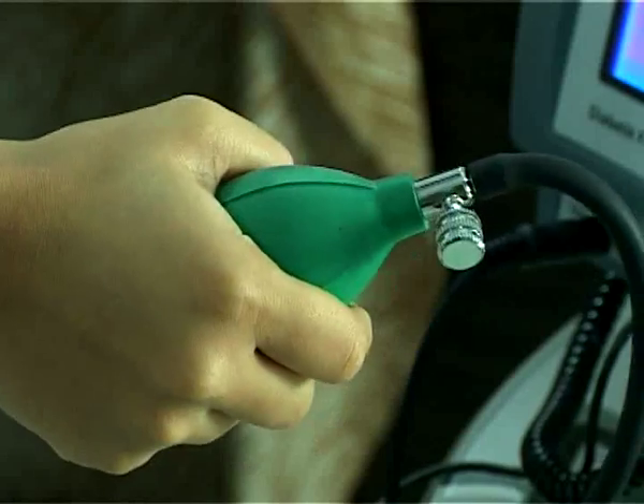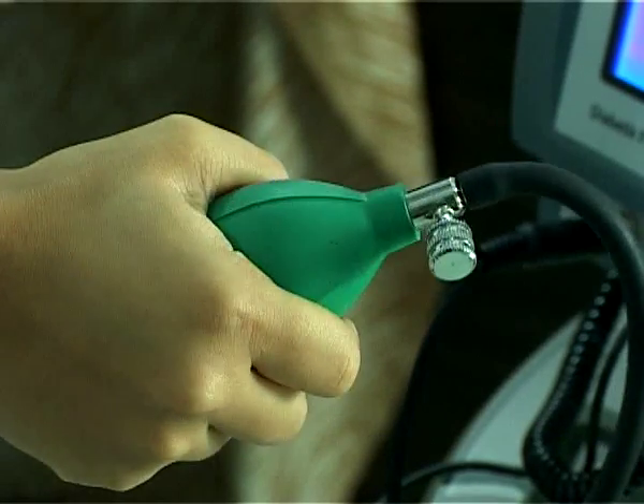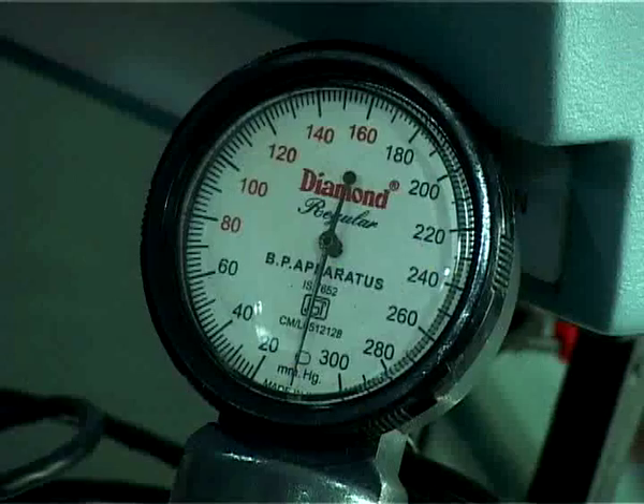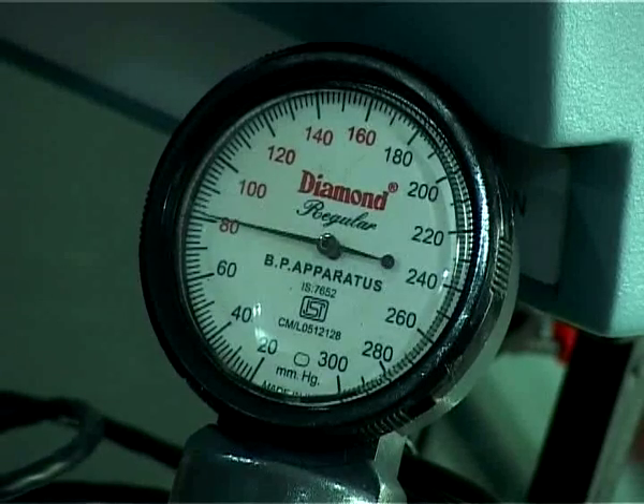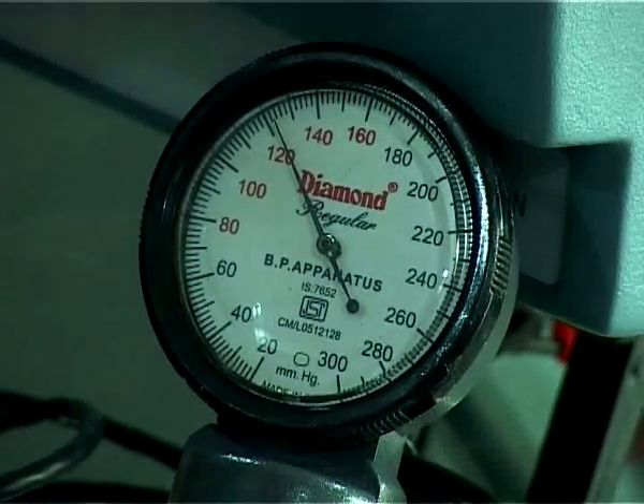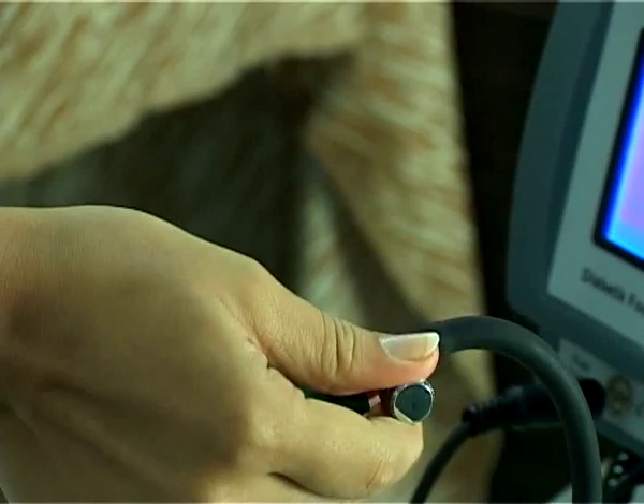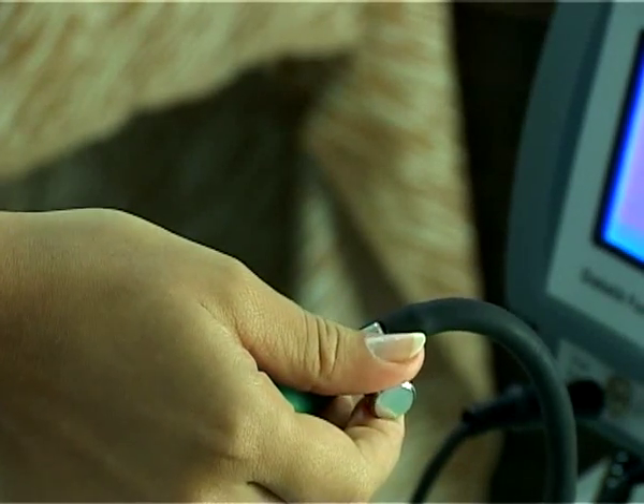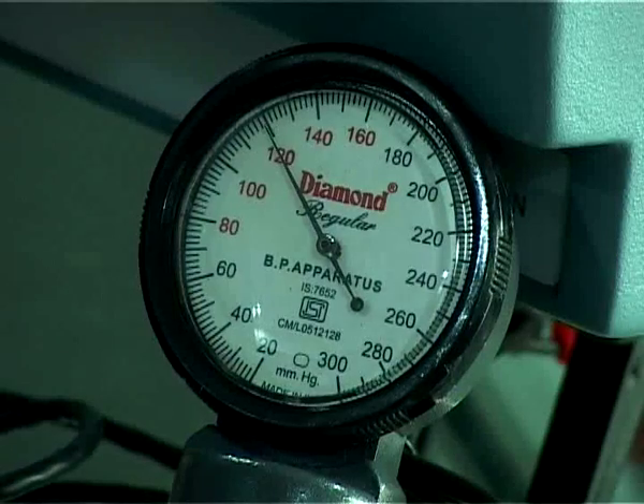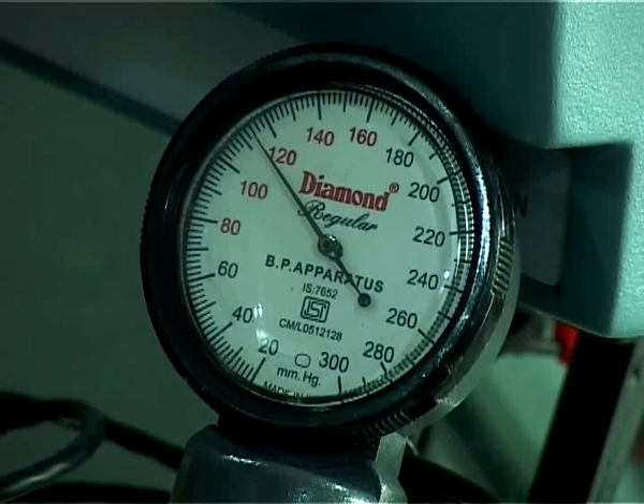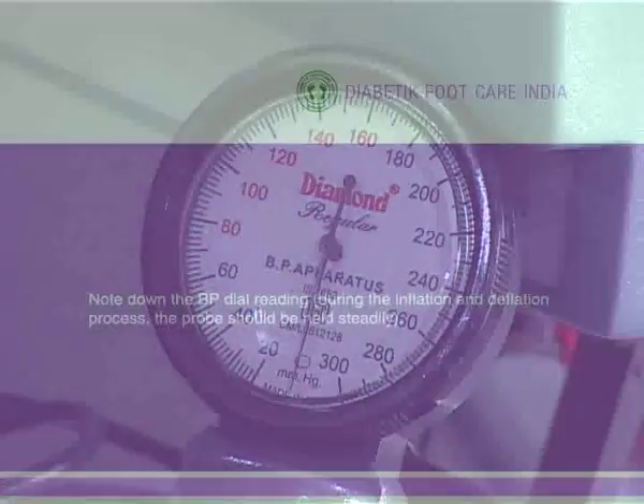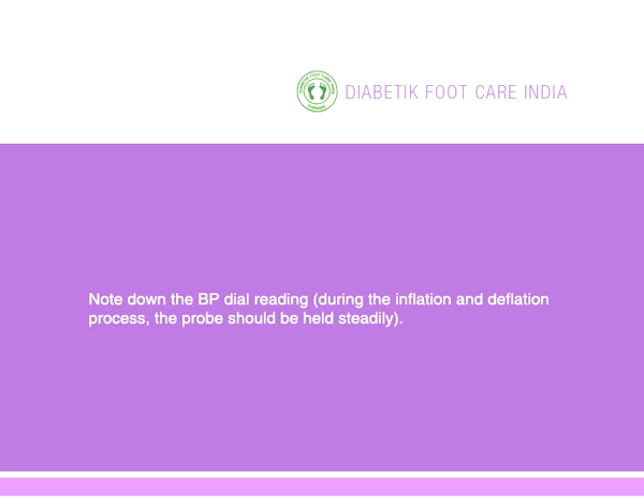Inflate the cuff until the Doppler pulsatile multiphasic sound stops. Slowly deflate the cuff until you hear the first appearance of the sound. Note down the BP dial reading. During the inflation and deflation process, the probe should be held steadily.